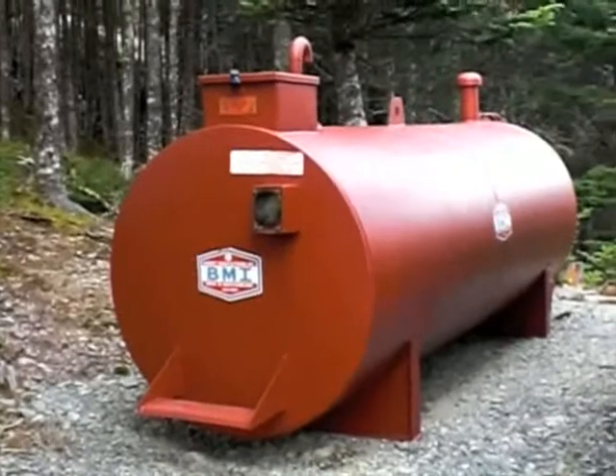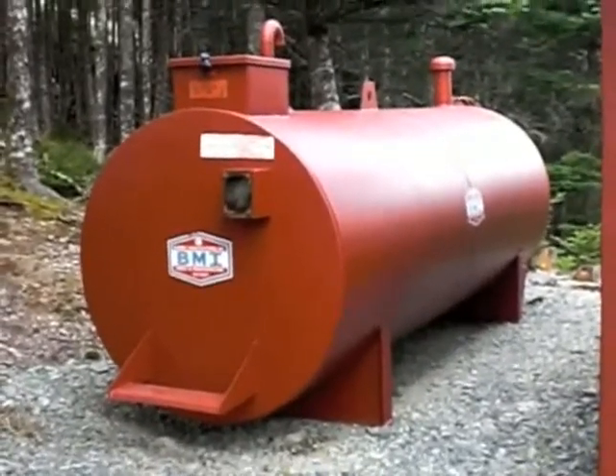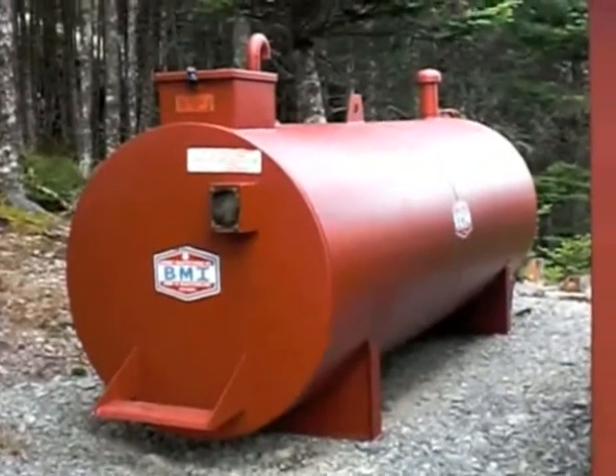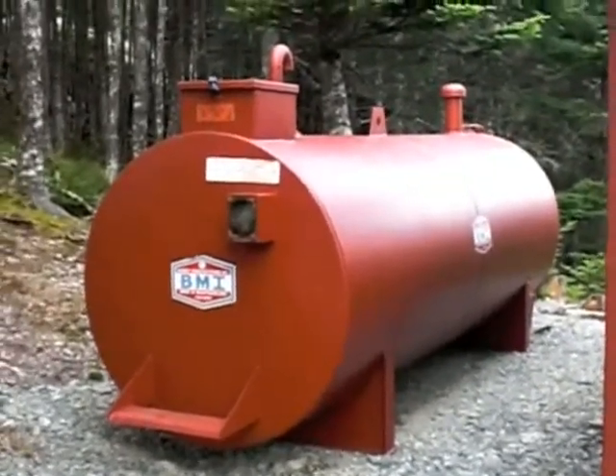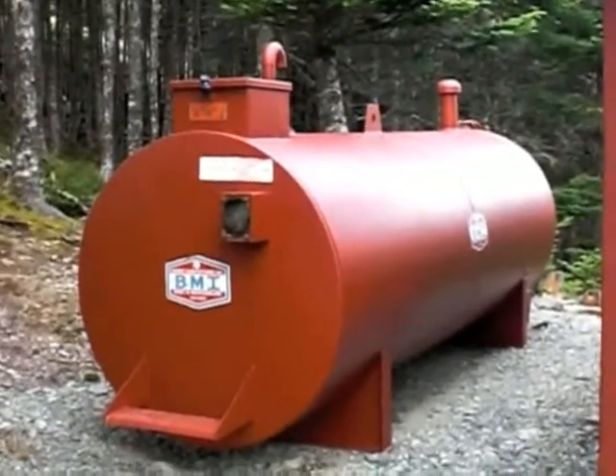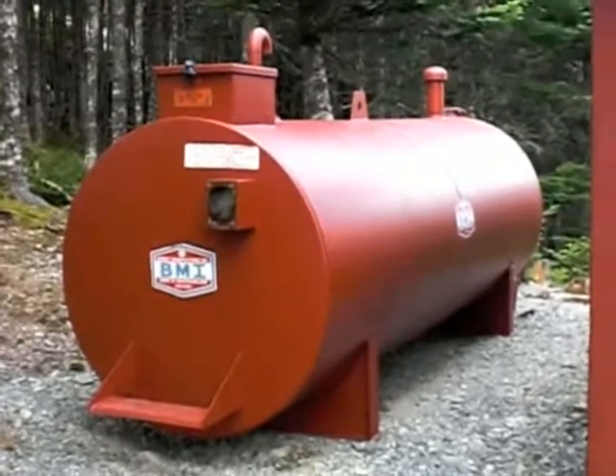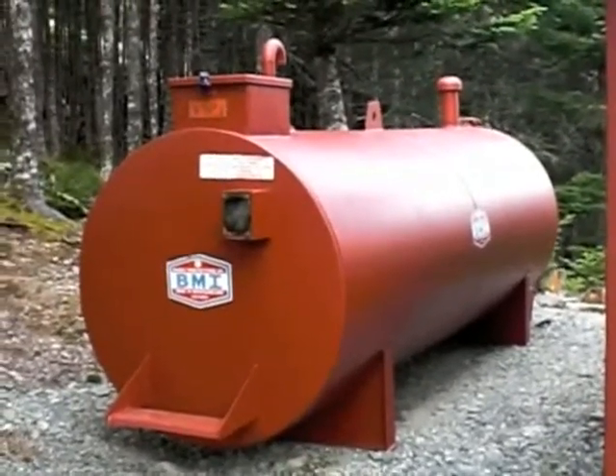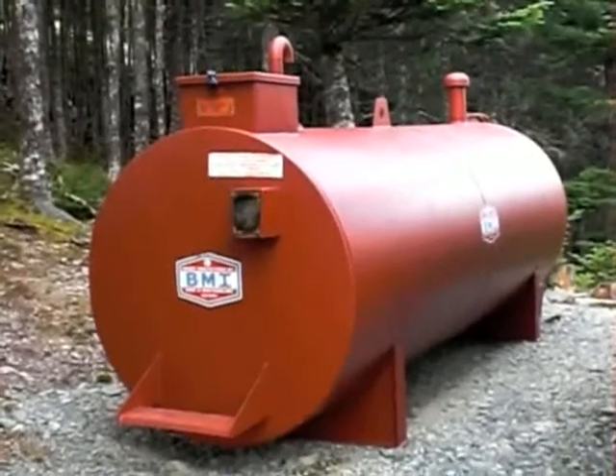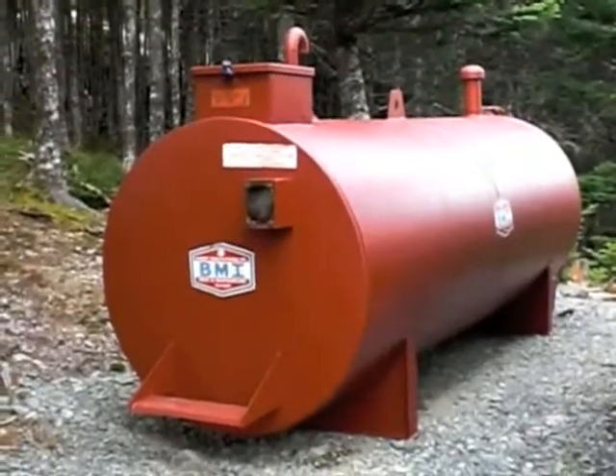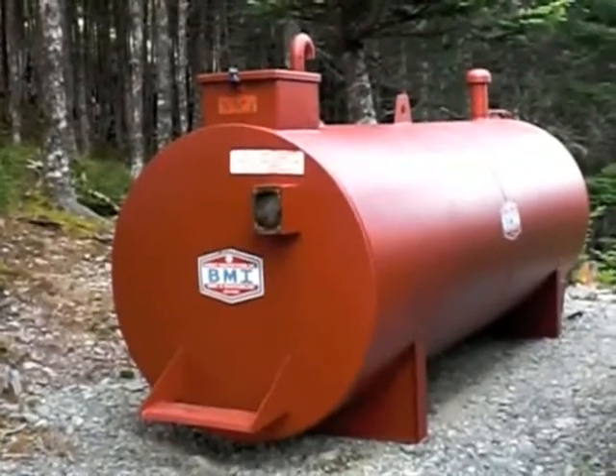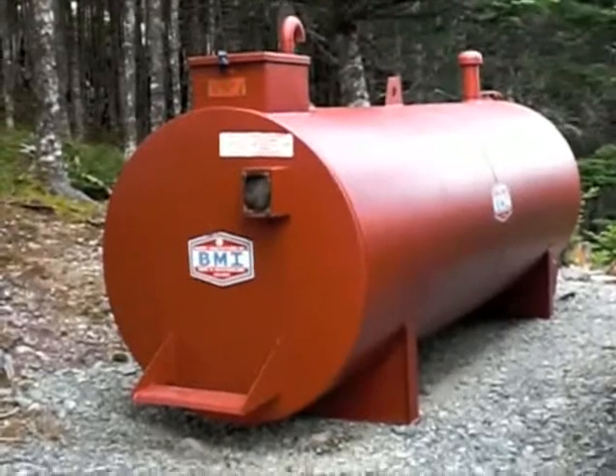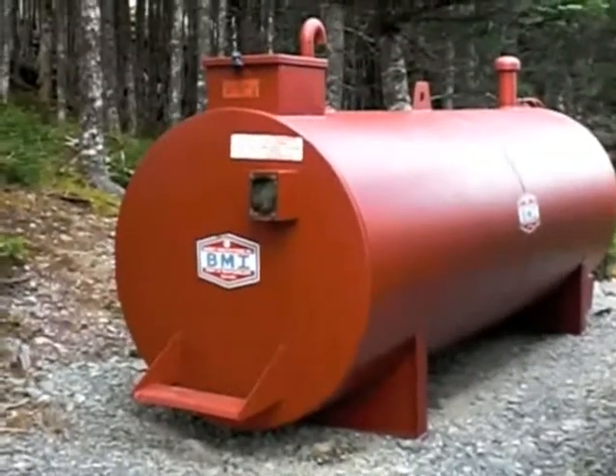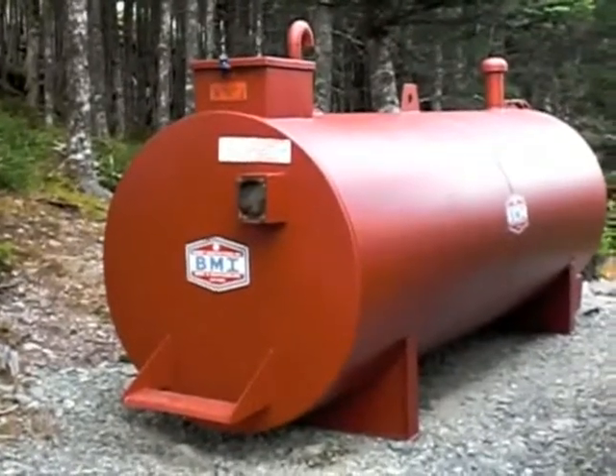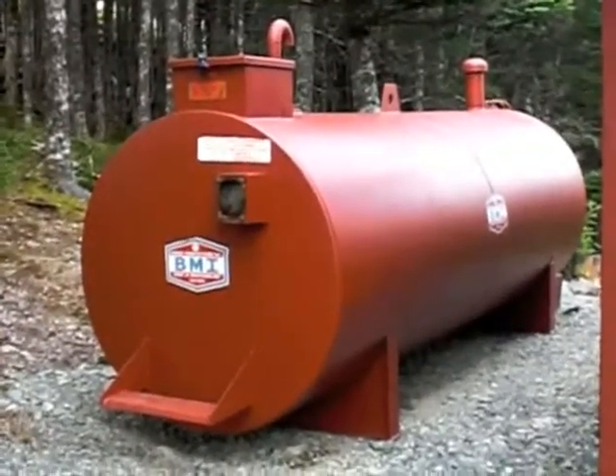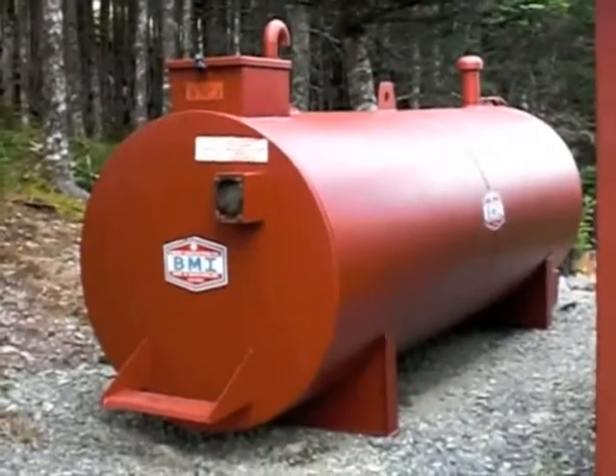And when they have the guests in, we're running the generator 24 hours a day, 7 days a week. And when the maintenance staff are here on their own, they're burning that for approximately 10 hours a day. But now that the wind turbine system has been installed, it seems that they haven't burned a liter in about a week. So they were going through 2.5 liters per hour. It was measured just earlier this year that they're going through about 2.5 liters per hour. So you can see that already we've offset a lot of diesel fuel being burned here at this location by installing these windmills.